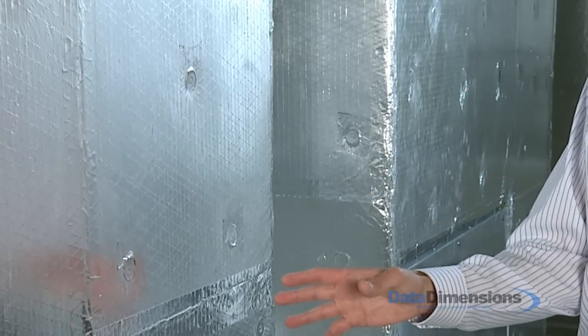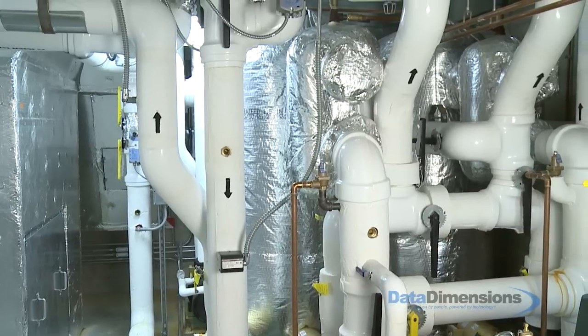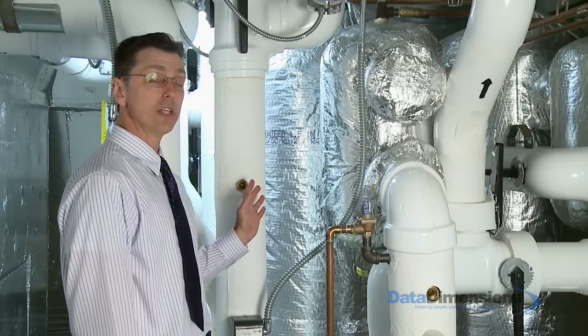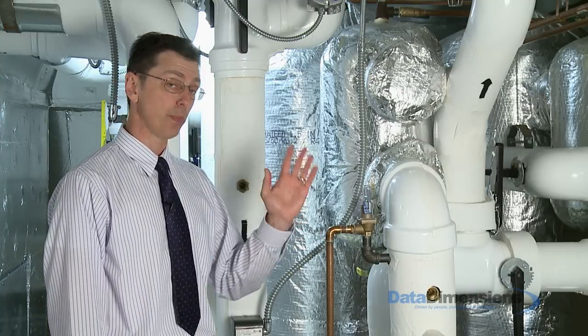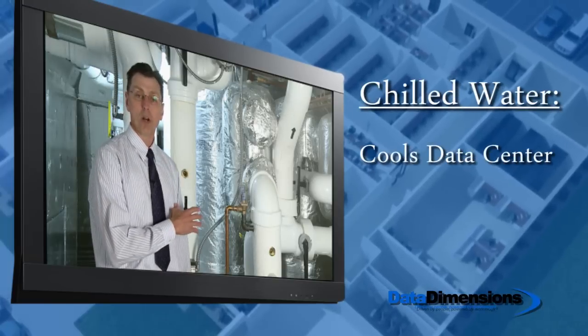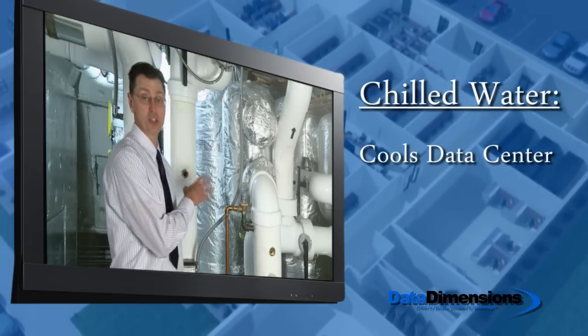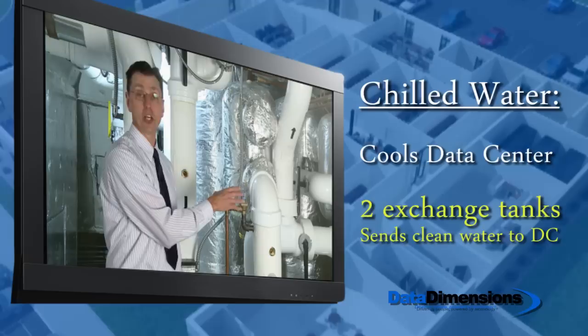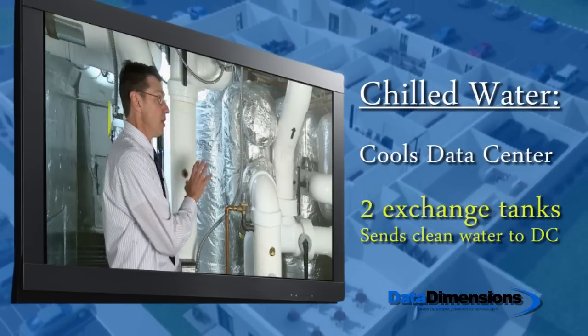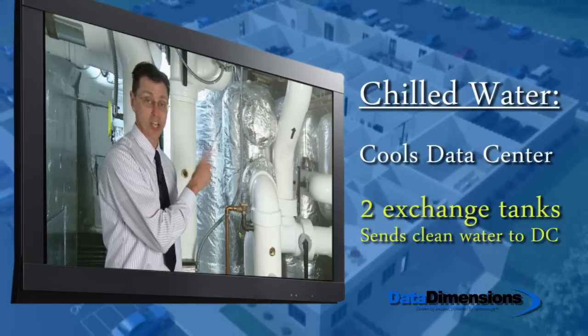We're still in the basement of the facility, and below the data center here is where we provide the chilled water. Chilled water is essential in order to keep your components cool inside your data center. I've got redundant chillers here, each on its own separate loop, each with a separate digital scroll compressor as well as a standard compressor inside of them. We can do lead lag across each of these, providing chilled water up to the data center. The chilled water, as it leaves the chillers, circulates through these two exchange tanks and then is pumped up into the data center space. Once we get that water out of those chiller systems, we have it exchanged in these tanks behind me. We have one as the primary, the other is the secondary, and they can operate in lead lag functionality. That way we have clean water heading up to our cooling units that are in the rows up in the data center.